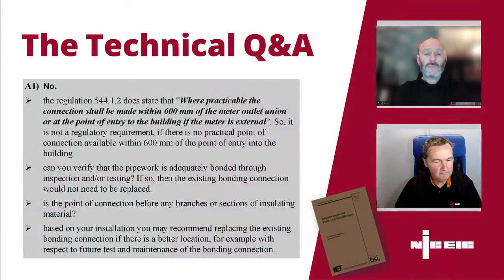In a nutshell, no, there's no blanket requirement to replace it. The regulation says the connection shall be made within 600 mil where practical or practicable, so there's engineering judgment involved - it doesn't have to be spot on 600 mil. If there's no practical point of connection, it could be made at a different distance. The thing to do is verify the pipe work is adequately bonded through inspection and/or testing.